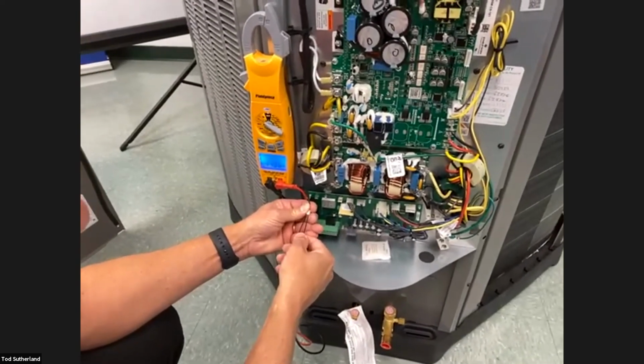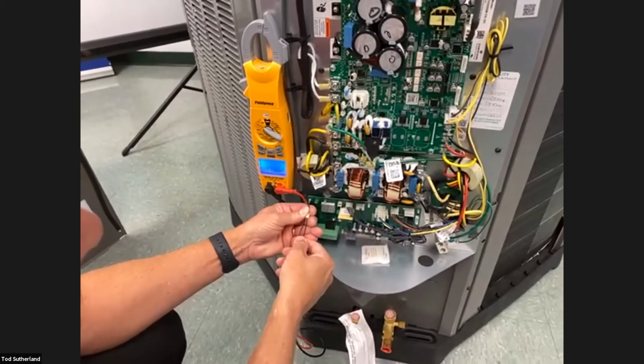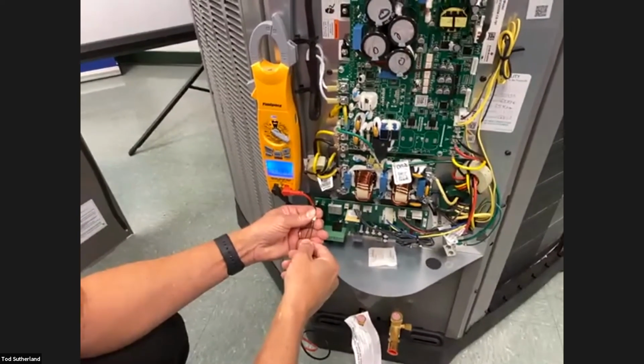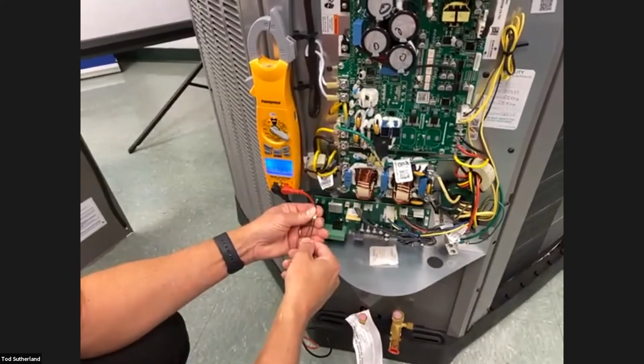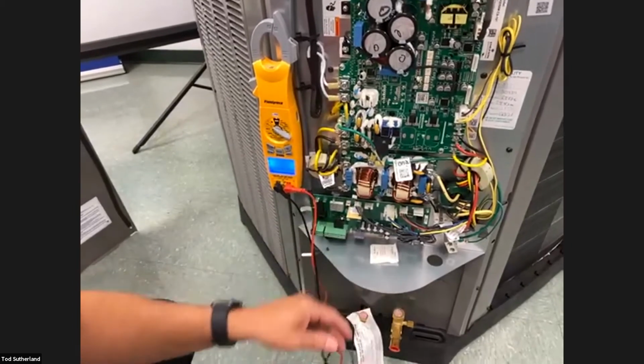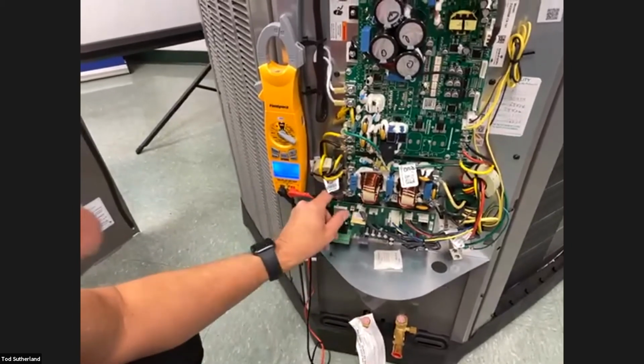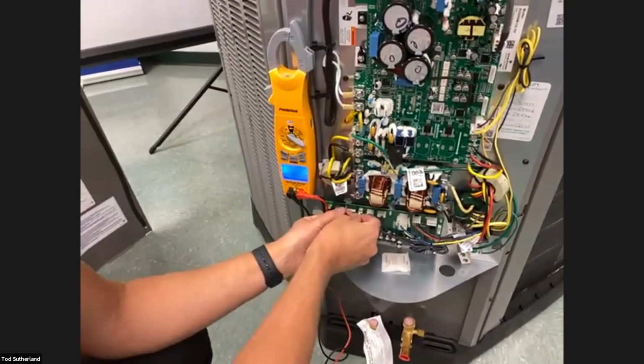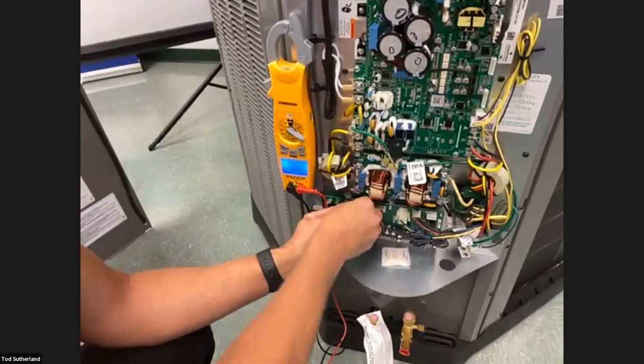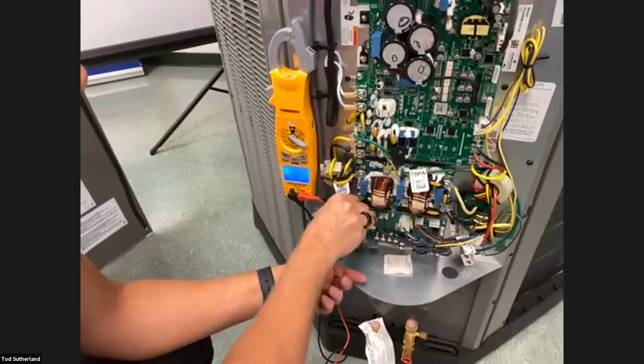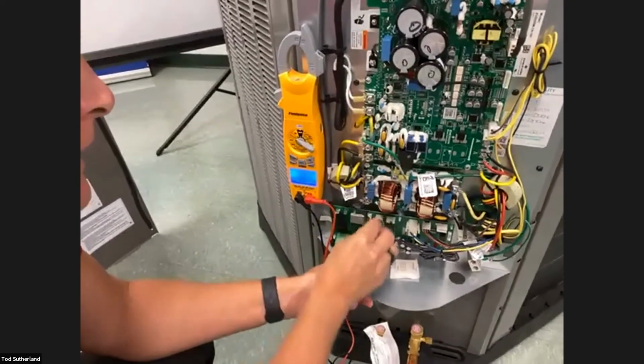So we're at 11.36K ohms. If that's 11,360 ohms, and you take your 10K ohm chart and look at that, you're going to see that that's probably about 75 degrees, which is what we have the temperature at inside this room. Okay, so we test that. We know that that thermistor is fine.